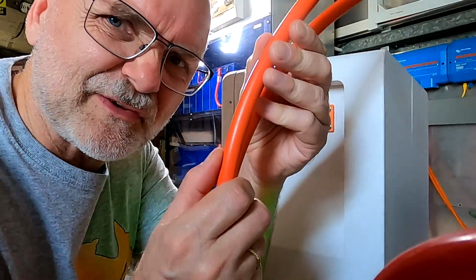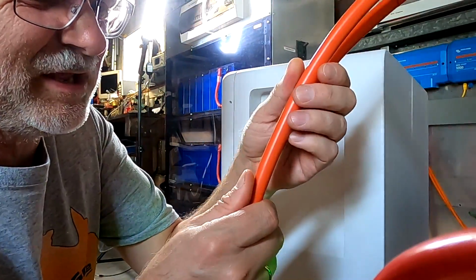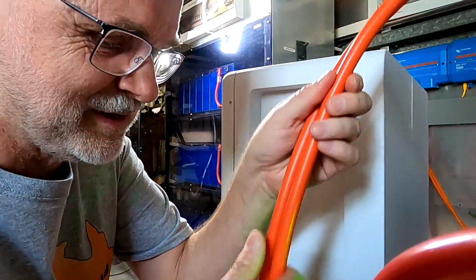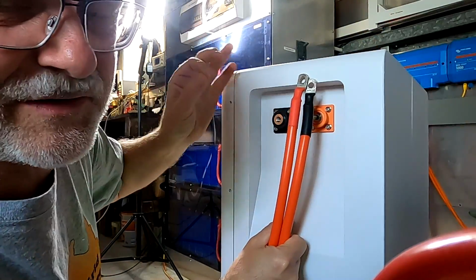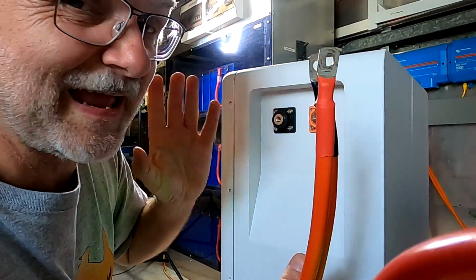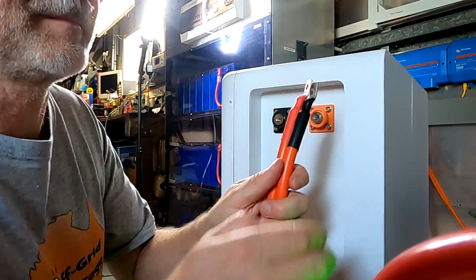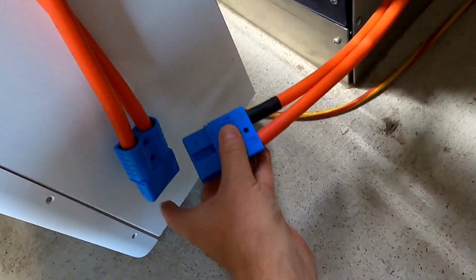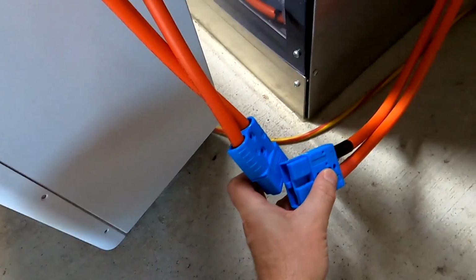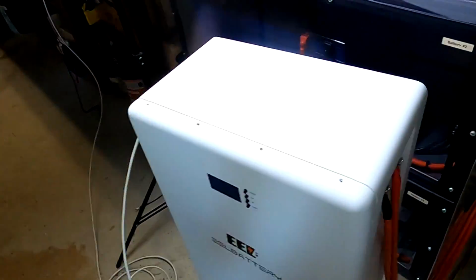I don't actually think this is 50 mil cable here, I think this is only 35 mil. But up there it's protected with a 63 amp circuit breaker, so the cable is totally fine for that. So we can connect these two together now. The circuit breaker is still off, there's no power coming in. Quickly connected, everything is good.